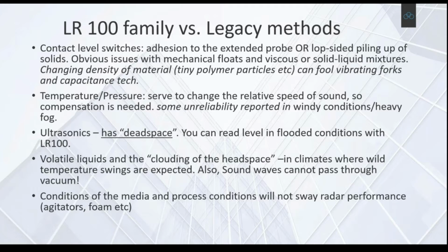As I mentioned, with volatile liquids in certain places, like a desert outpost where it's -10 at night and +30 or +40 in the day, something like diesel will probably boil off even if it's in a sealed system. As it reaches midday, high noon, it will boil off, and there'll be a much more cloudy blanket that would fool the ultrasonic - previously it would read the top of that blanket rather than the top of the actual fluid itself.